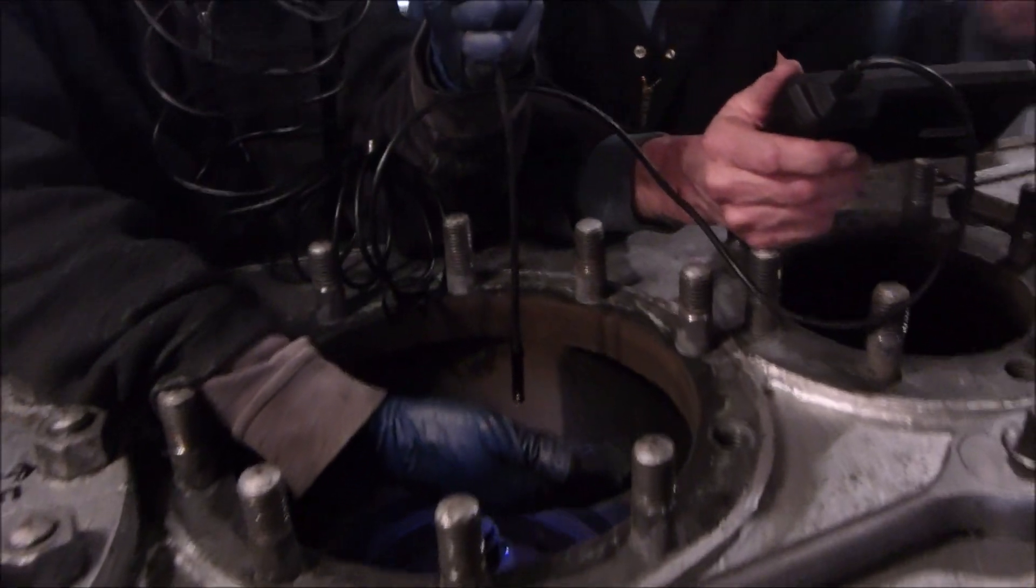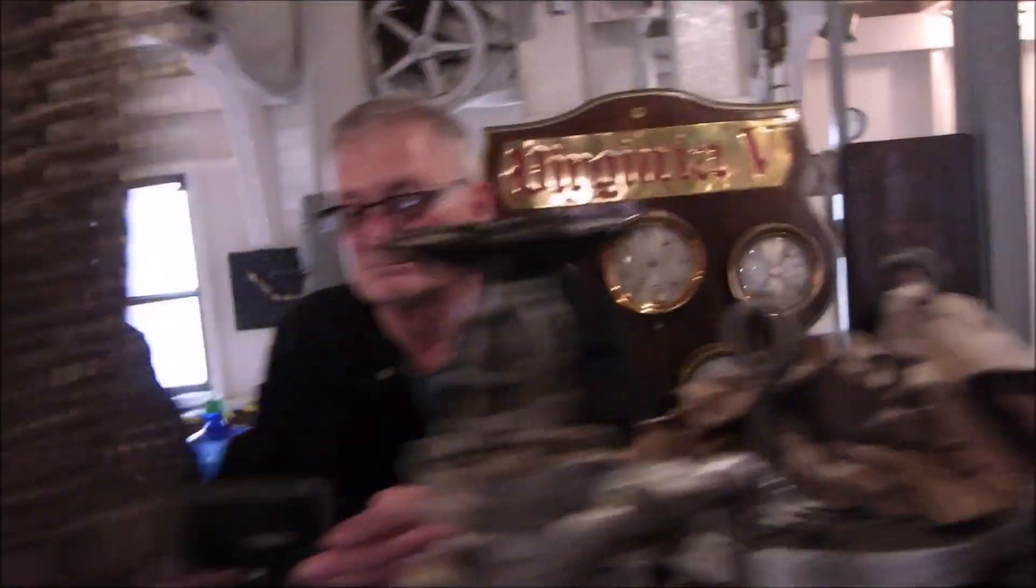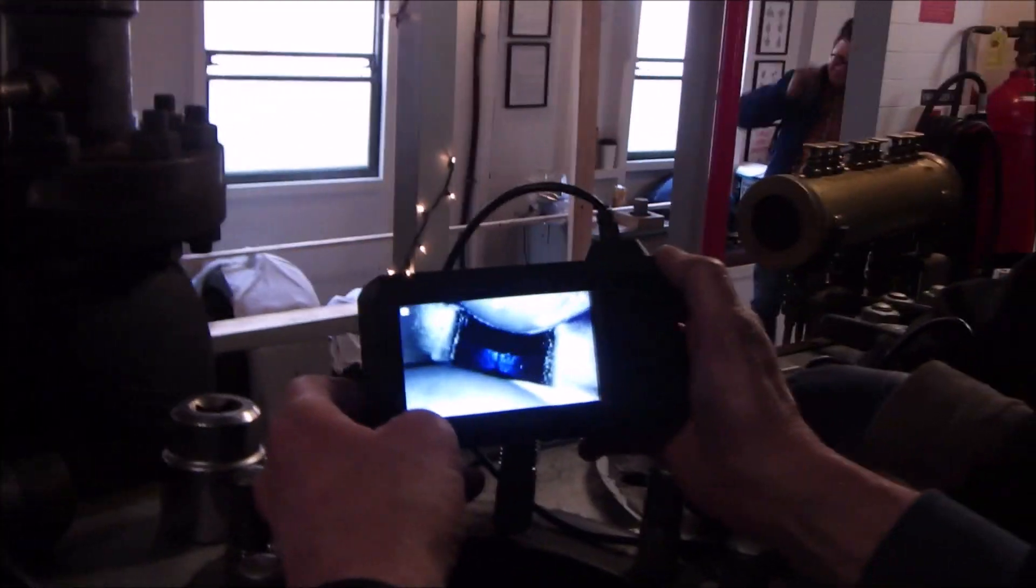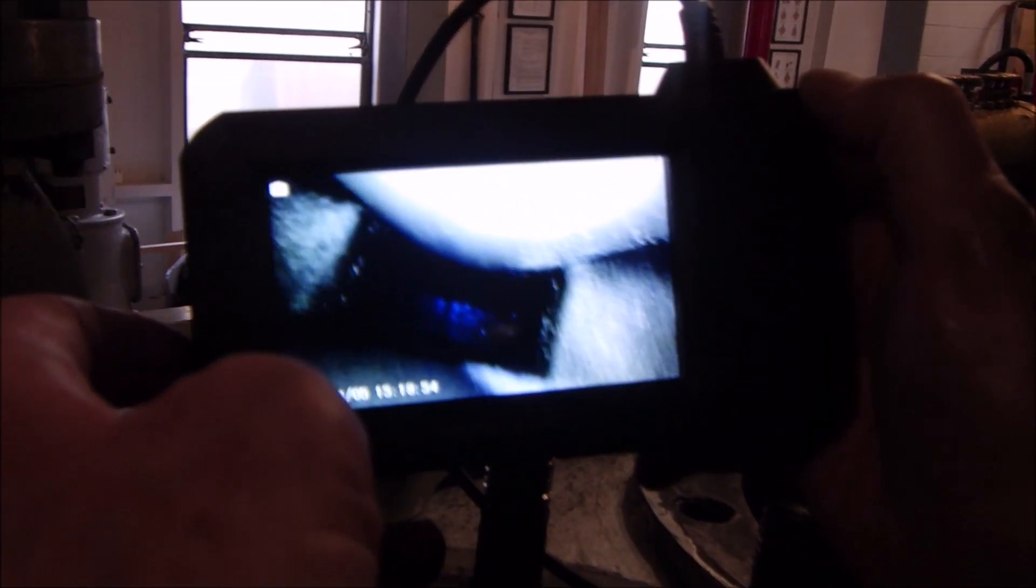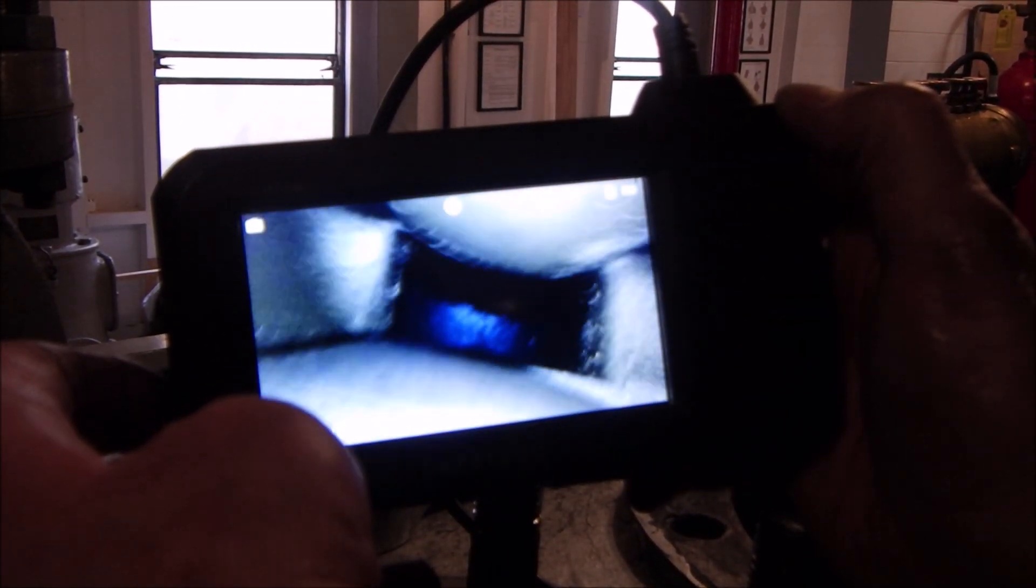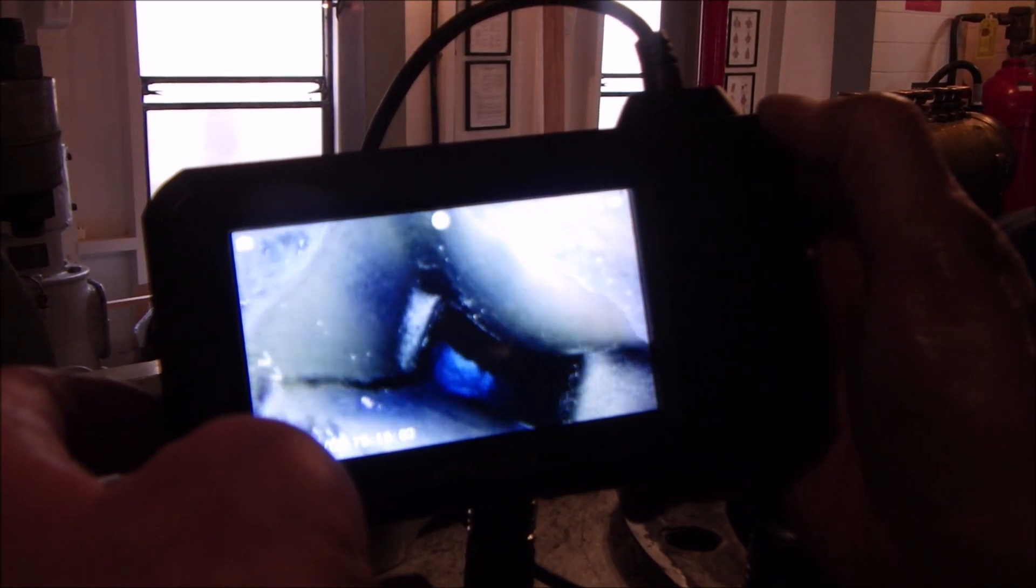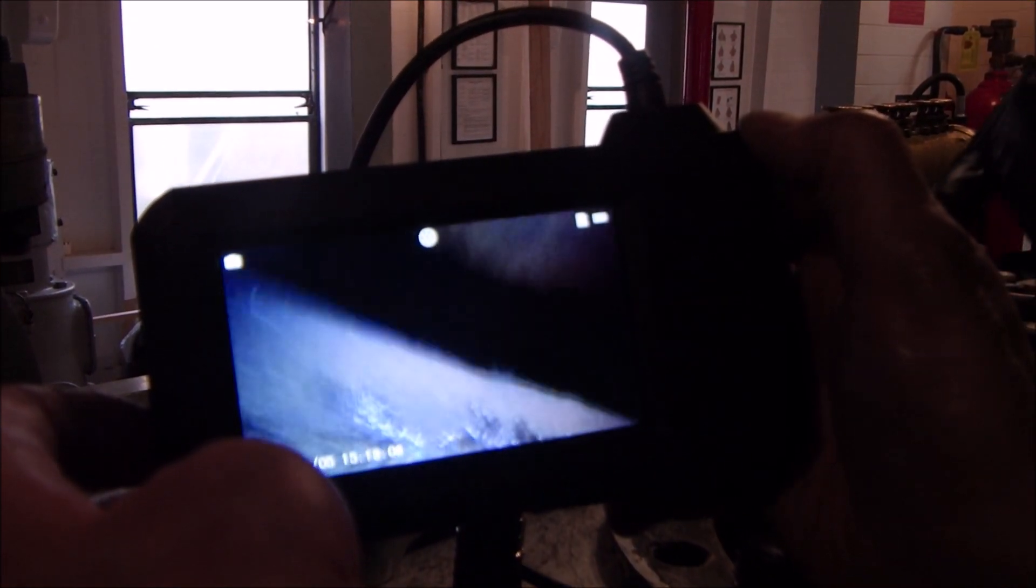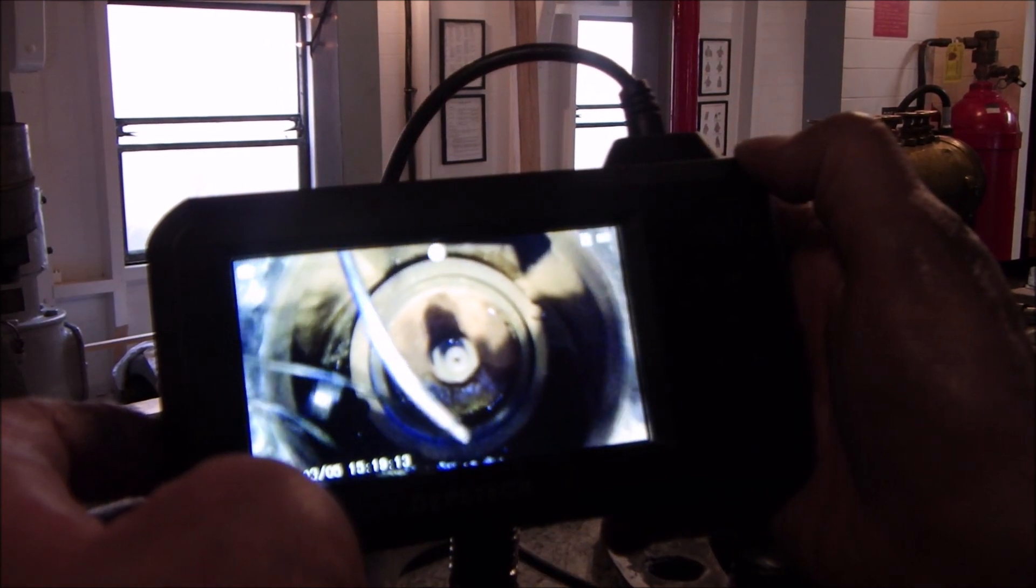And one of our final tests is going to be running a boroscope down in here to get a look inside the valve channels and make sure there's no debris blocking them. So we're looking into the intermediate pressure valve cavity. Can you zoom out and look at the top of the piston just to kind of get a perspective of where we're at.